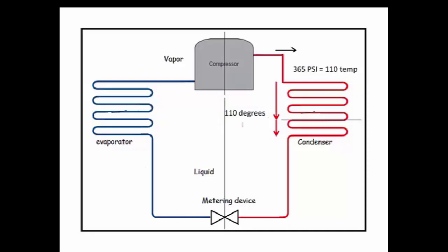It does that above the line. Once it gets below the line, then it starts to give off additional heat in the form of sensible heat. So between the black line and the bottom of the condenser, it will give off another ten degrees of subcooling, and it will exit the condenser at 100 degrees. Thus we have ten degrees of subcooling.